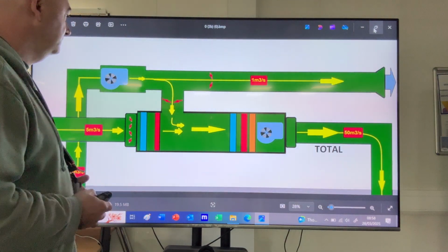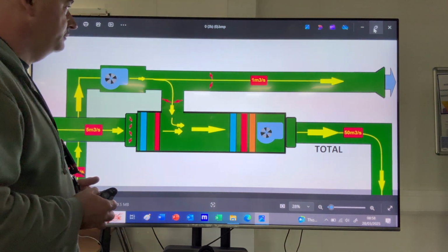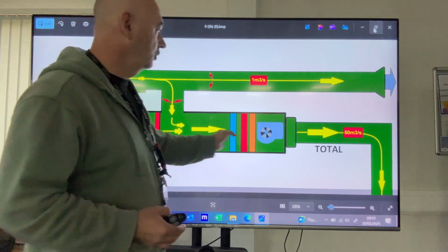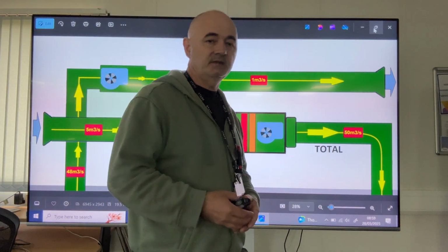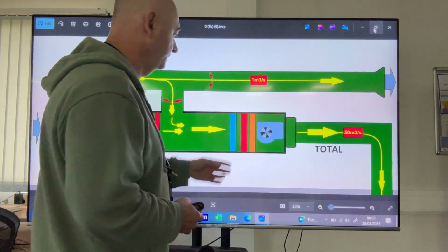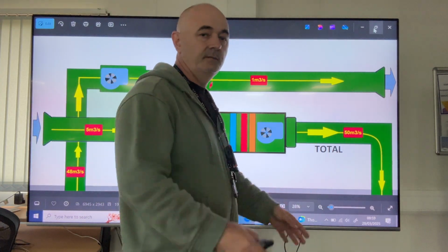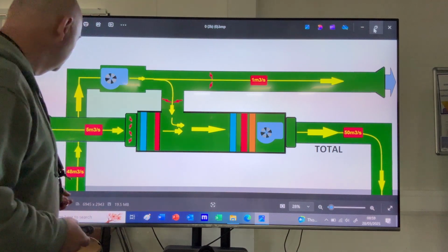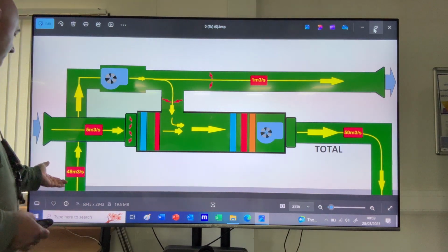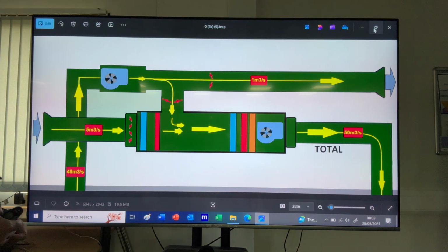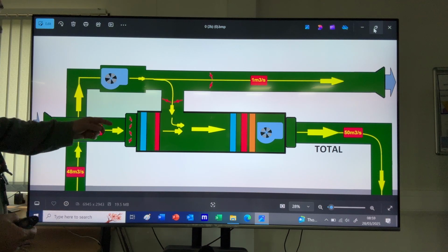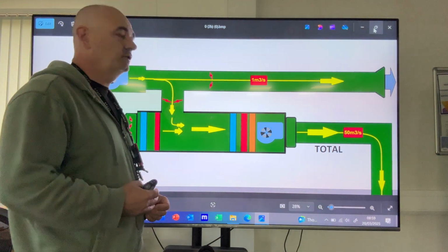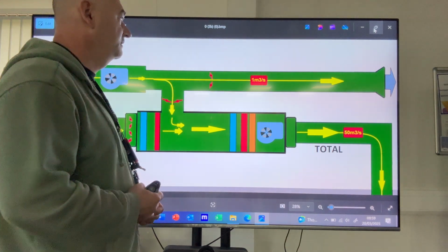Now you will see better. This is the type of AHU we use and what we monitor. We have global airflow. You can see here 50 cubic meters per second. There it goes into the many branches which direct the air into the rooms. We extract a quantity of air like 48 cubic meters per second, and we bring 5 cubic meters per second fresh air, and we exhaust 1 cubic meter per second.